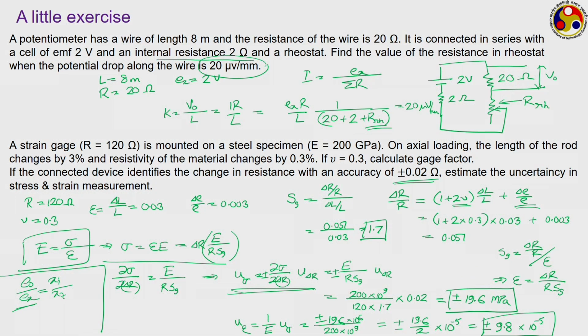Whatever power it is going to dissipate, the excitation voltage has to adjust accordingly, and also the value of resistance. We know if P represents power, that will be equal to Ex square by R, so the voltage Ex should be equal to root over RP. Since P is the power that is generally specified, and we generally can't go to very high power levels, whatever may be the value of RP, Ex has to be adjusted accordingly, and we can't just put any high value of Ex.